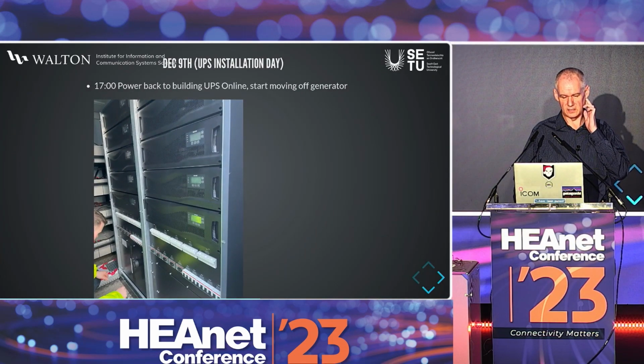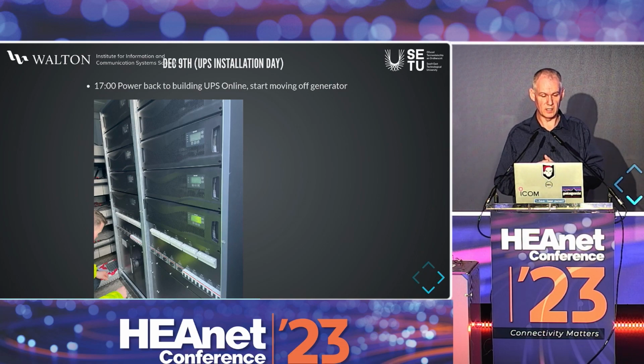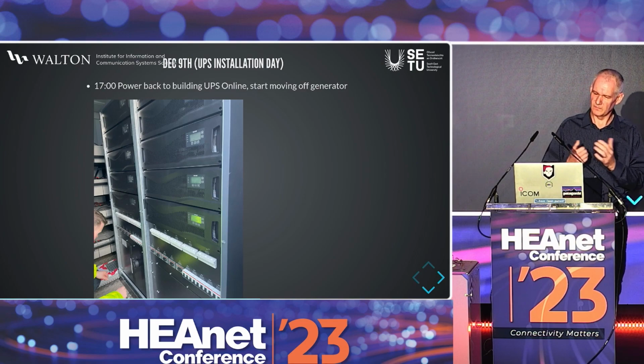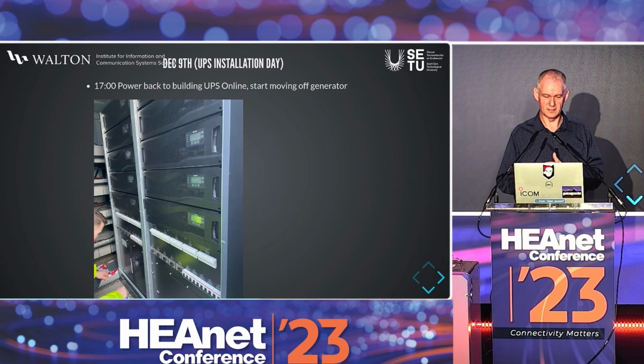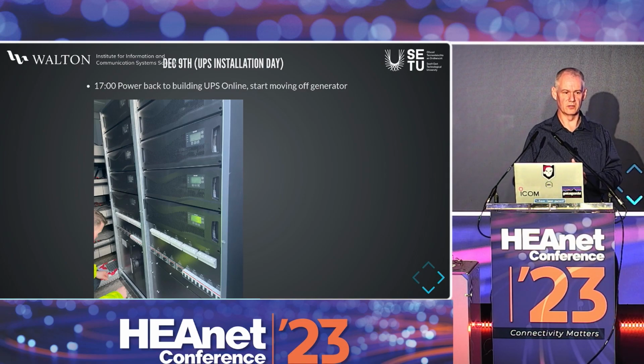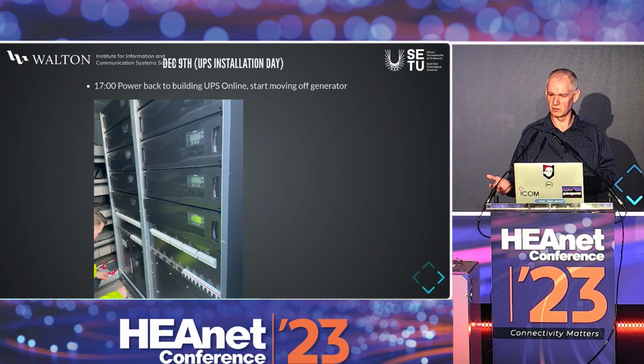That's the inside of the UPS itself. By 5 o'clock that day, the UPS was in and wired. It had to warm up - I didn't know that, none of us knew this. We had to let it warm itself up before it would come online fully, because the batteries were cold from being in storage.